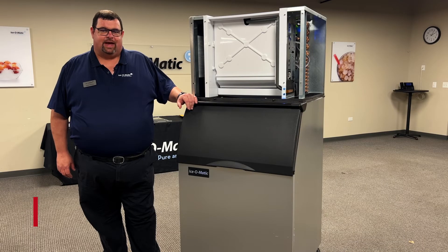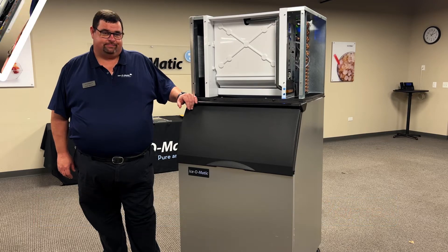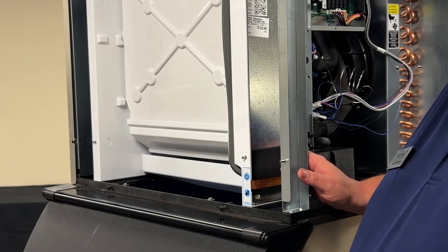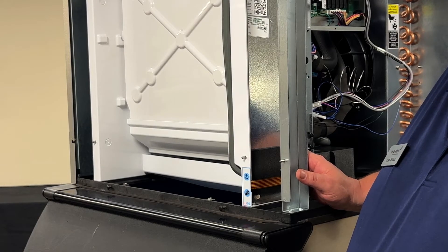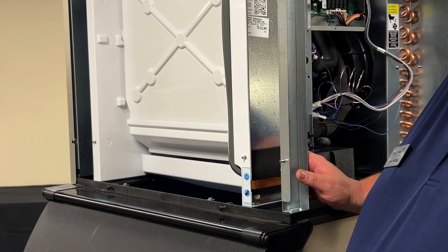Hi, I'm Josh with Ice-O-Matic. We're going to go over some CIM error lights today. This is error code number one, which is a maximum length freeze cycle. Maximum length freeze cycle on these machines indicates an hour-long freeze cycle, followed by a harvest of less than five and a half or seven minutes, depending on which board you have.